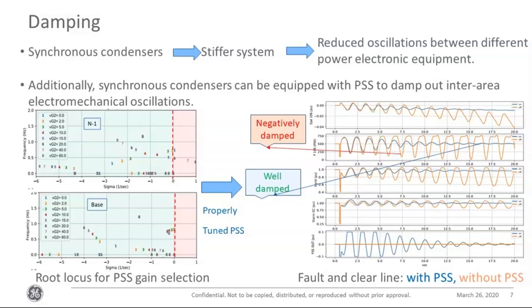And you can see the results on the right, where there was a fault and then one of the lines was cleared. Without the PSS, that's in orange, you see these negatively damped oscillations. With a properly tuned PSS, that's in blue, the oscillations are very well damped. And the damping gets even better if, so there were multiple SCR synchronous condensers here, and the damping was better if both were equipped with PSS as opposed to only one. So that's an example where we were able to equip the synchronous condenser with PSS and effectively damp out an inter-area mode of oscillation.